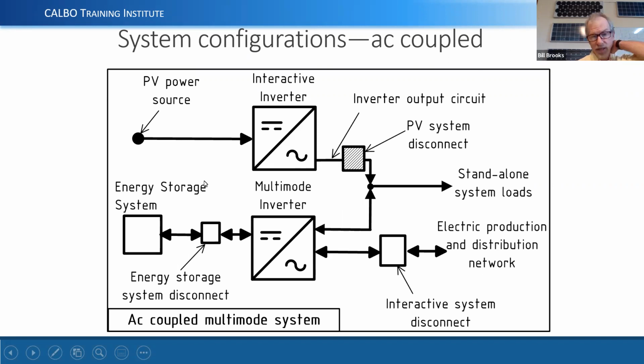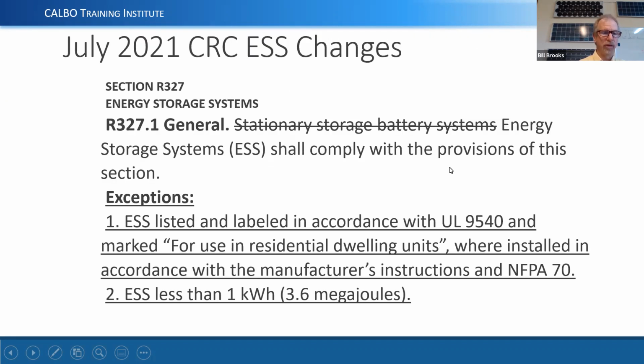Of course, if this was a Tesla system, then the inverter is incorporated into the Powerwall, and then they connect the Powerwall through what we call a microgrid interconnect device, which in their case is called a Gateway. Enphase calls it their Smart Switch. SolarEdge calls it their Backup Interface. Franklin calls it their aGate. There are all these different products out there that provide that microgrid interconnect device in a separate enclosure, which isolates that whole portion of the house from the utility grid. In a multi-mode inverter, that microgrid interconnect device is inside the inverter. And there are actually two AC outputs, one on the grid side of the microgrid interconnect device, and the other on the backup load side.